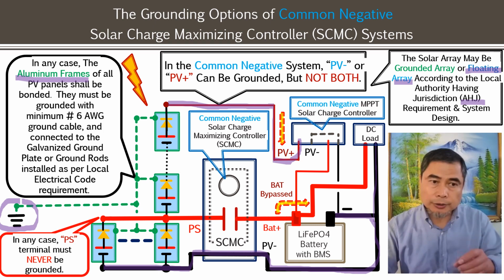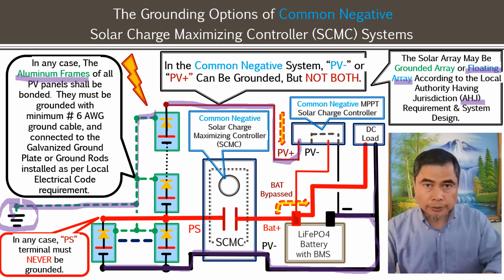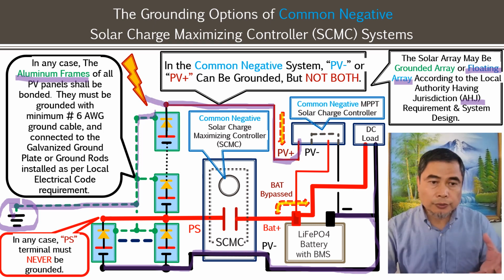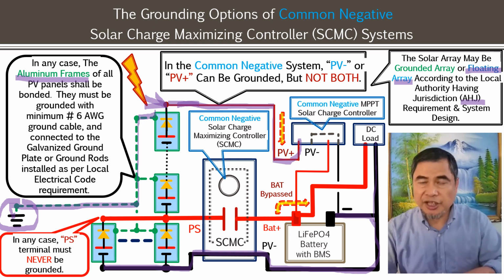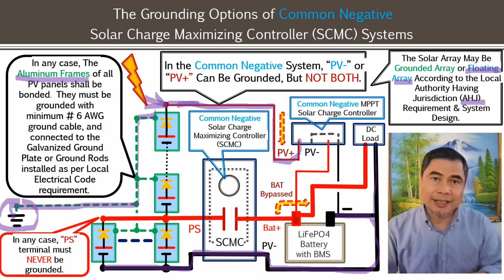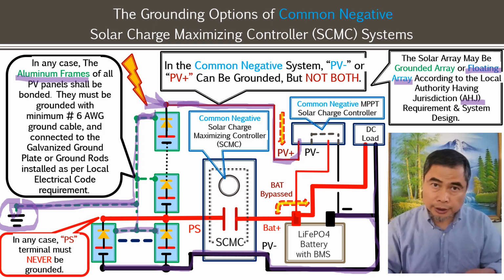You want to make sure that in case of lightning, this high current can be conducted through the ground cable to the earth. It will not allow this high voltage to shoot through the system. If you don't have that, the chances are you would have that lightning high voltage going through the PV positive or PV negative, or PS, and then further to all the components inside the house, causing a lot of big damage. So this frame, in any case, must be connected to the ground or joined together.